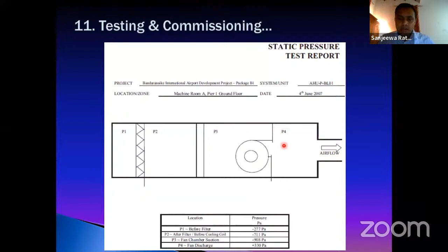Right. Next, this is the static pressure report. Here you see P1 and P2, that's the pressure difference between the filters, and P3 is after the coil and P4 after the fan. All the pressure readings are taken with the pitot tube, and all are tabulated here. And at last, as a summary, all those things are given. This is the design volume, and whereas you get a volume of 94%. The recommendation is also given separately.